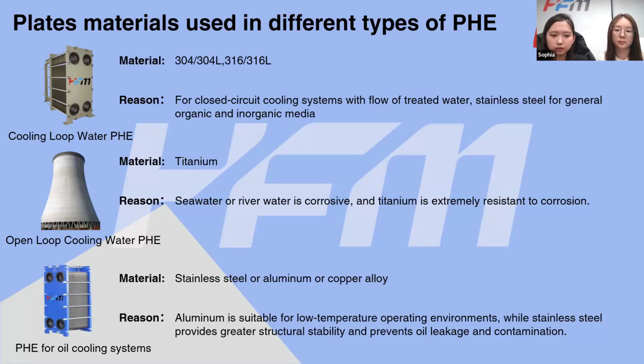So the last one comes to the oil cooling systems. The oil cooling system material is stainless steel, aluminum, or copper alloy, because oil cooling systems require high structural stability, and stainless steel, aluminum, and copper alloy can provide good strength. Aluminum is suitable for low temperature, while stainless steel provides better protection against oil leakage and contamination. So by choosing those materials precisely, we ensure that each heat exchanger provides optimal performance and durability in specific operating conditions.